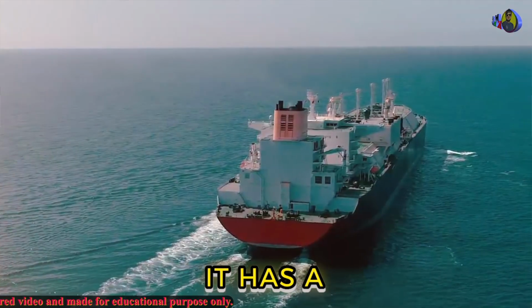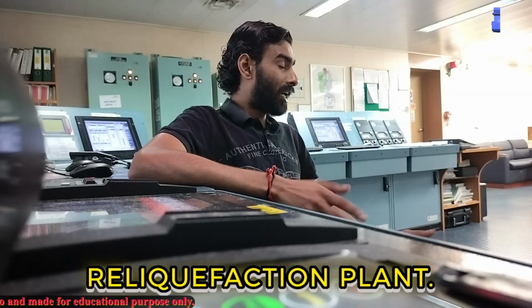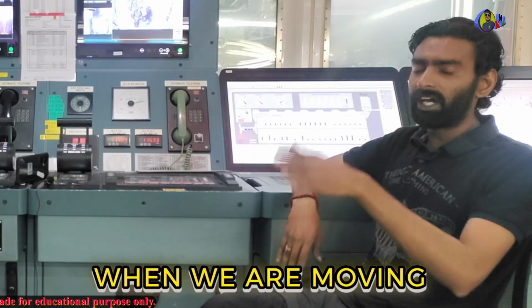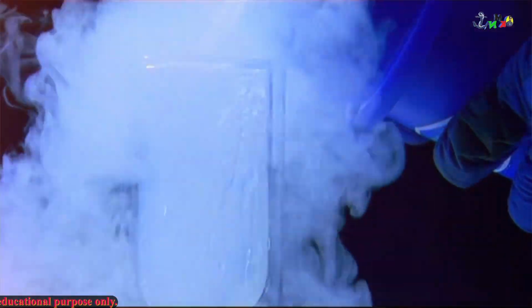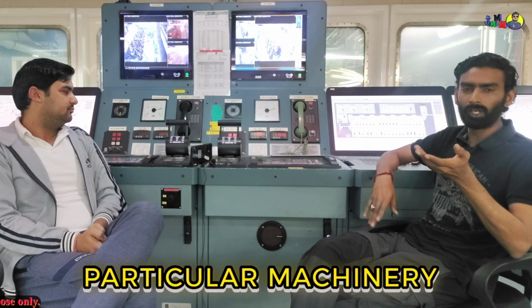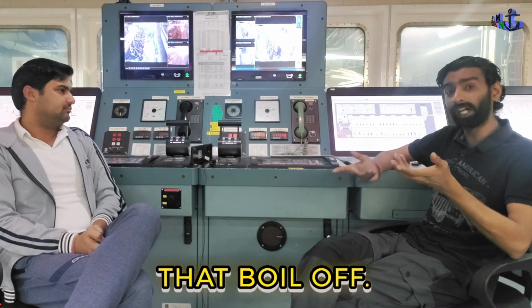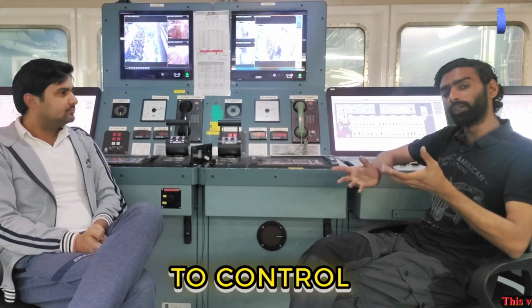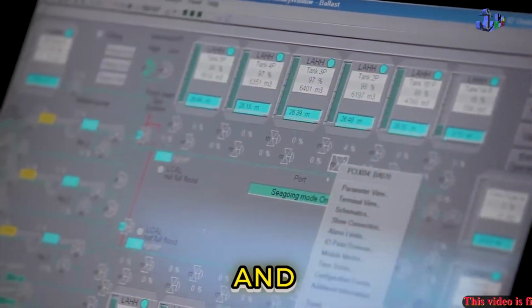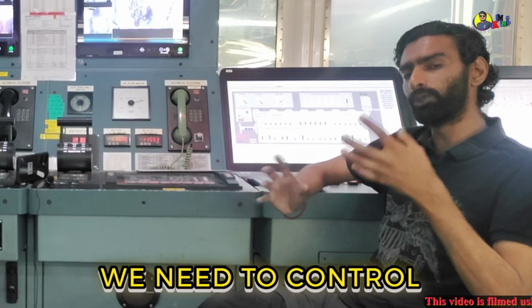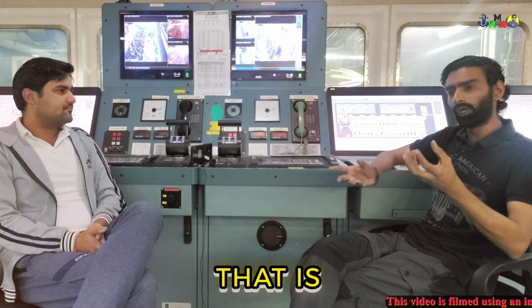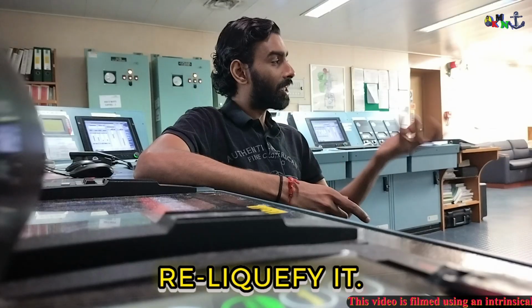Especially on this vessel, it has a re-liquefaction plant. So when we are moving, the LNG boils off. Whatever boil off is there, we are not consuming it because there's no particular machinery designed to consume that boil off. So in order to control the tank pressures and temperatures, we need to control that boil off, and whatever boil off is generated, we need to re-liquefy it.